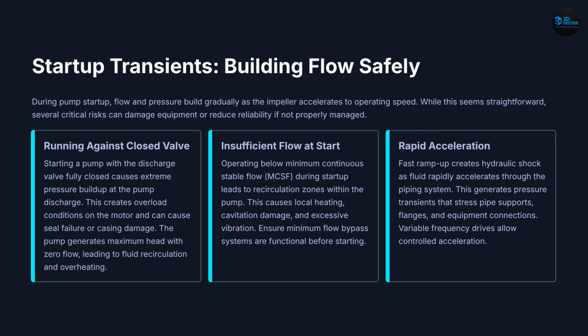Startup risks. During startup, the pump accelerates and builds pressure gradually. If the discharge valve is fully closed, pressure builds rapidly and can damage the pump. If flow is too low, internal recirculation causes heating and vibration. Rapid acceleration can also create hydraulic shock.